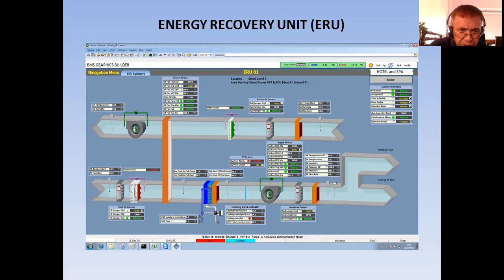air handling unit. Now, as you can see here, I have the typical points for monitoring and control. So here you can see I have two fans. One is the supply fan and one is the exhaust fan. Okay. Now, this one is the heat pipe. Okay. Now I have the cooling coil, but I have a wrap around heat pipe also. Then I have the three dampers with damper actuator. Then I have the filters. Okay, then I have some temperature sensors, a combination of temperature and humidity sensors.